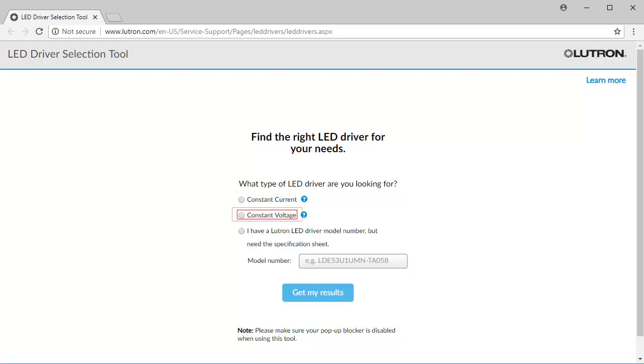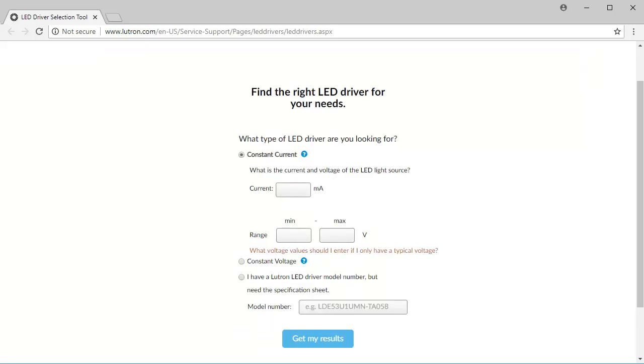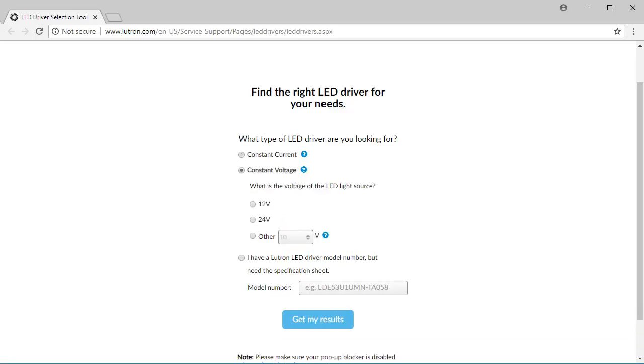To understand this, you must have access to the LED specification for the load you are trying to control. If your LED light source is constant current, you will notice one value for current. If your LED light source is constant voltage, you will notice only one value for voltage, likely 12 or 24 volts.